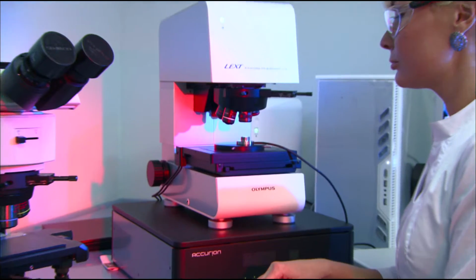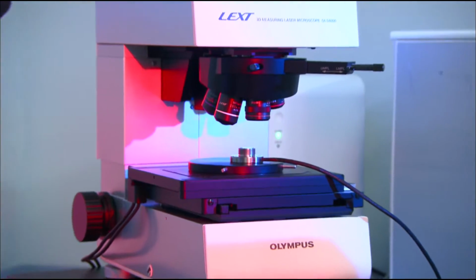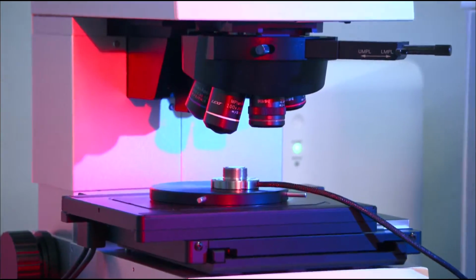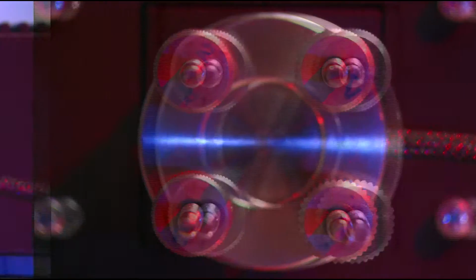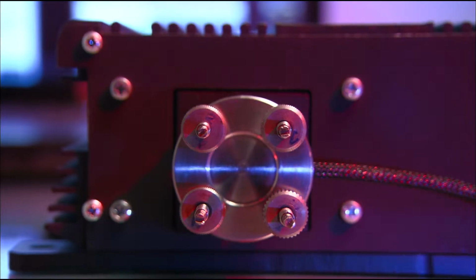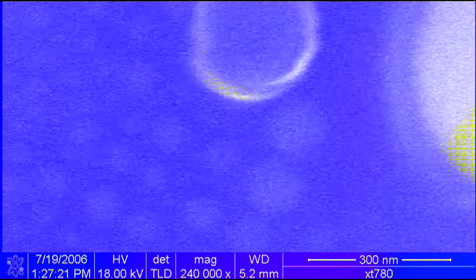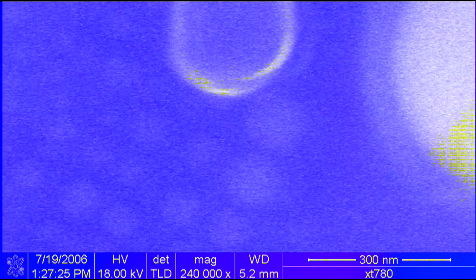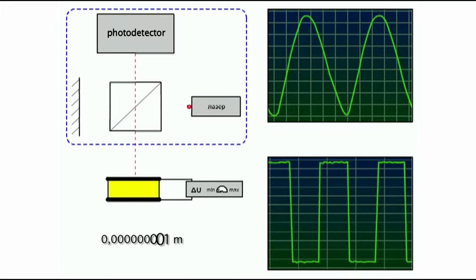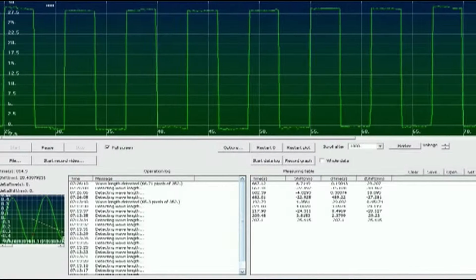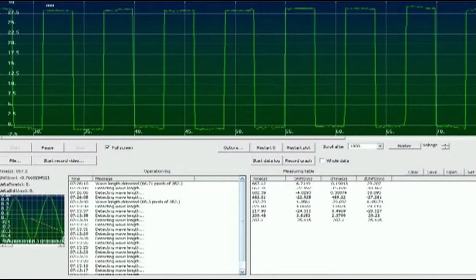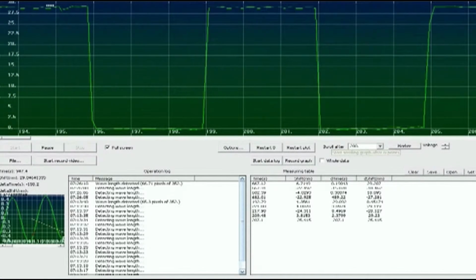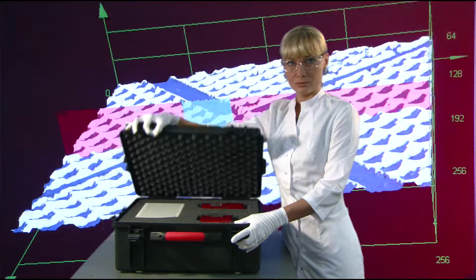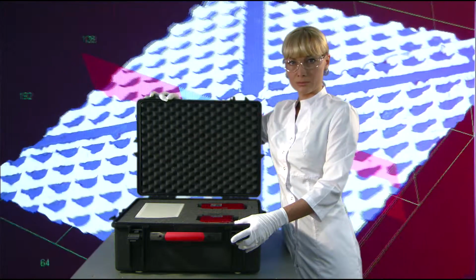Samples can be used for calibrating scanning microscopes, electron microscopes, and optical interferometers. Other devices can also be calibrated using the nanosamples. In addition to Nano Standard, a new high-precision interferometer was developed, which measures the movements of nanosamples in nano units. The measurement uncertainty is so small that it cannot be even measured in nanometers. Besides this, the interferometer can be used separately for measuring the movements of nanomanipulators, sensors, and biological objects. Our system of measuring devices is shipped to you in a standard hermetic container.